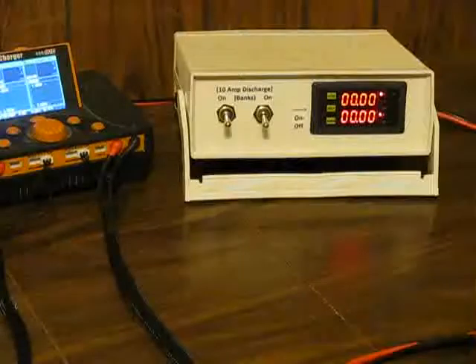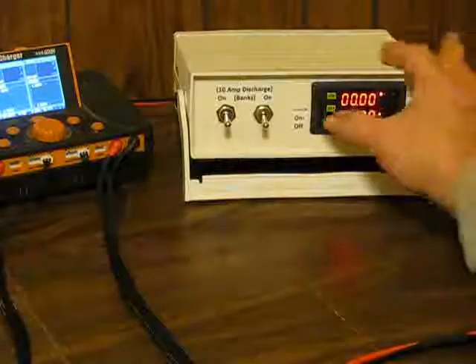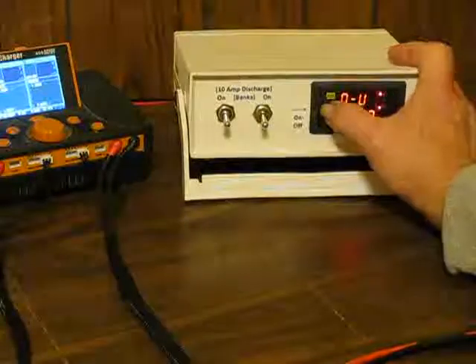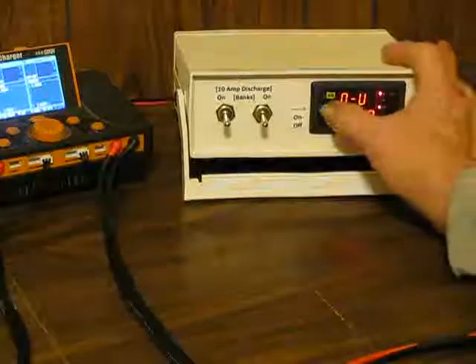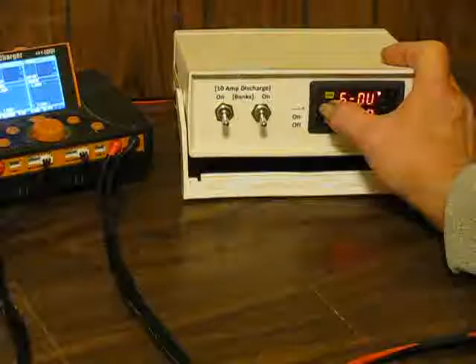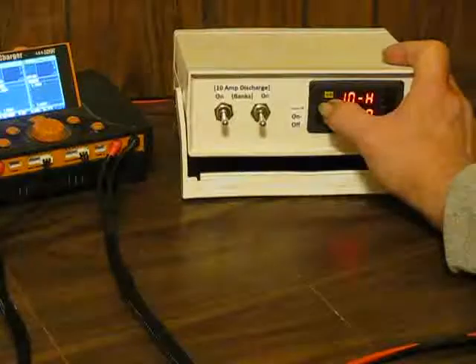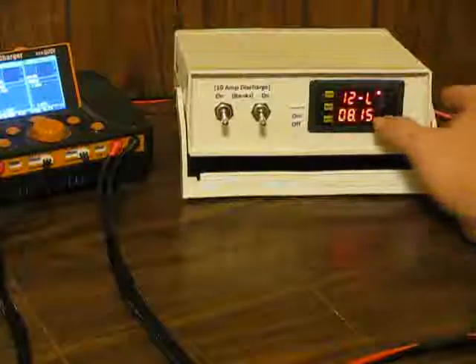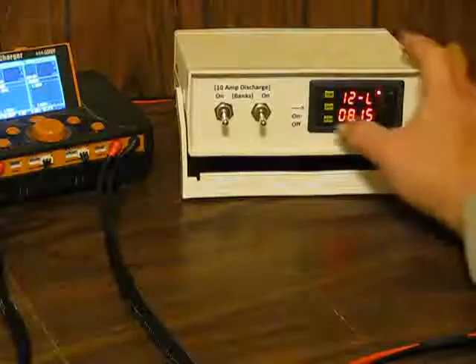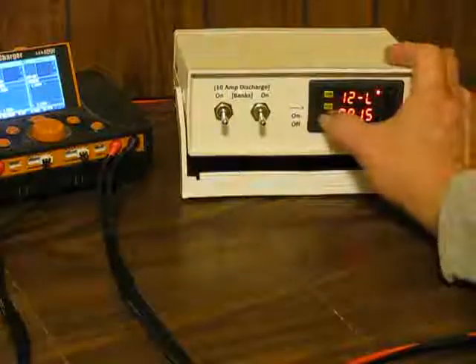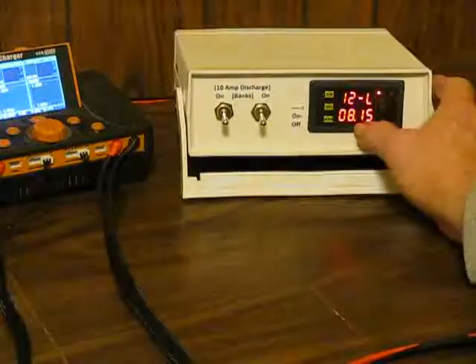Now we'll have to go through and change a couple settings. Hold down the center button, get into the adjustments, go up to setting... actually, no, setting 12, sorry about that. That was where we set the low voltage shut off. We'll take that down to 6.97.